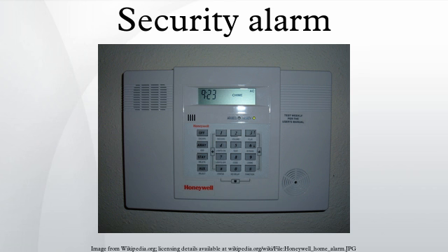Prior to the availability of dual signaling systems, police and keyholders were often called out to the premises because of an alarm signal on the telephone path, only to discover that it was a network fault and not a genuine alarm. Dual paths allow distinction between hardware failures and a genuine attack on the alarm. This helps eliminate false alarms and unnecessary responses. Dual signaling has helped considerably with the restoration of police responses in an instance where a phone line is cut, as the dual signaling device can continue to send alarm calls via one of its alternative paths, either confirming or denying the alarm from the initial path.